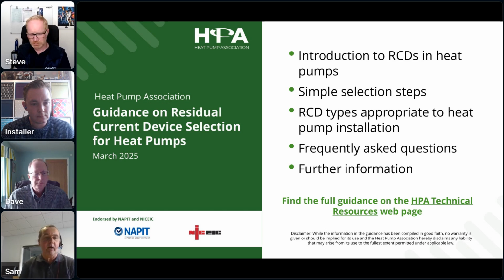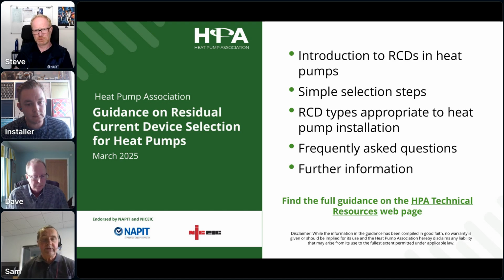The obvious example is IT equipment, for example, runs with a small leakage current. And so if you put the wrong size RCD on that IT equipment, it will result in the RCD tripping, even though there's no fault. It's normal operation. So that's one way that you've got to ensure that you select the right rating. And then the second way is that it's become apparent over time as RCDs have developed that there is also an element of DC leakage within AC and DC circuits. So some AC products and equipment produce DC leakage current, which can have the blinding effect that Steve talked about.